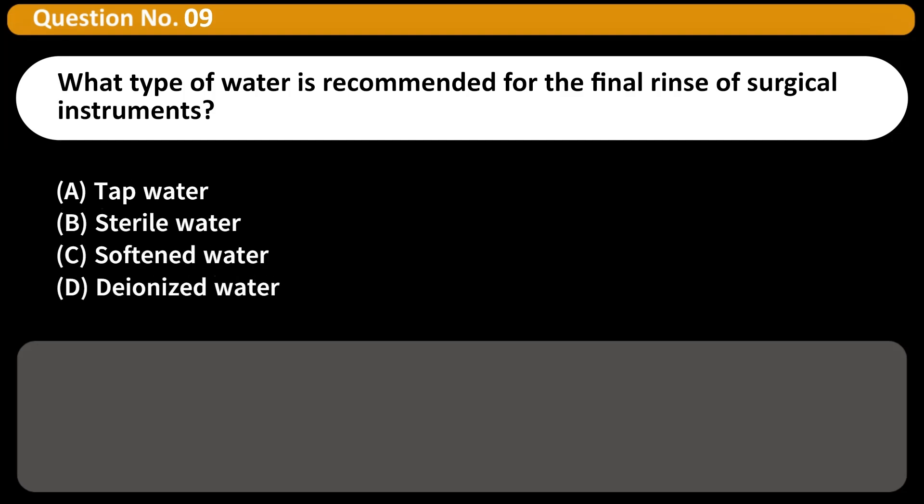What type of water is recommended for the final rinse of surgical instruments? A. Tap water, B. Sterile water, C. Softened water, D. Deionized water. Answer D. Deionized water helps prevent mineral deposits and spotting on instruments.